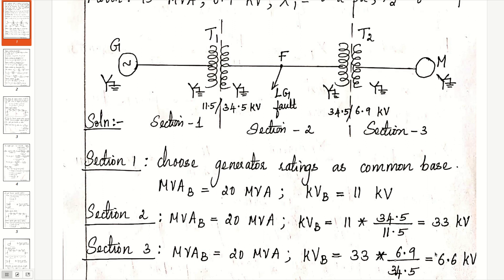Using the new base values in various sections, you have to convert the given per unit values of the reactances into the new per unit value using the formula: X per unit new is equal to X per unit old multiplied by (MVAB new / MVAB old) multiplied by (KVB old squared / KVB new squared).